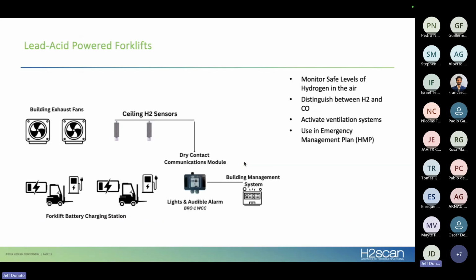Another application that we find a lot of sensing in would be forklifts. I mentioned I came from that industry, so it's an industry that has always just relied on its building exhaust fans, but now we're seeing the authorities are wanting some sort of sensing put in, and audible alarms that alert the operators that hydrogen has been accumulating. And so they're putting this as a part of their emergency plans. And again, if there isn't redundancy in ventilation, then a lot of authorities are asking for detection as the secondary, as basically the redundancy in the system.